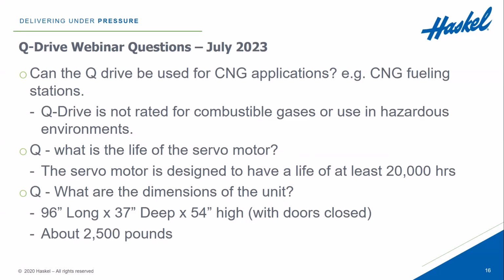What are the dimensions of the unit? Q drive is about 96 inches long, 37 inches deep, and 54 inches high with the doors closed. And as I mentioned previously, it has a weight of about 2,500 pounds. There's a little bit of plus or minus depending on the configuration, how many heat exchangers we have in there, and which gas sections we're using.